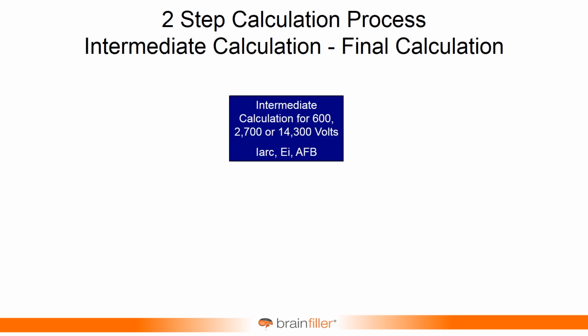So what happens, this is just kind of a simplistic view of how this plays out. You select the appropriate equation based on the voltages, 600, 2700, or 14,300 volts. And so there's three different equations. There's all kinds of coefficients that are going to be dependent on the voltage that you select. And you calculate the intermediate value, I call it the initial value, of the arcing current, the incident energy, and the arc flash boundary. And then for each one of these, you interpolate for your actual voltage. So as I mentioned earlier, let's say you use a 600 volt equation and you're calculating for a 480 volt system. Well, your initial calculations will be based on the 600 volt model, but then you interpolate and adjust this to the actual 480 volts.